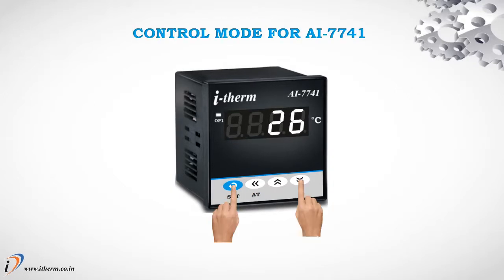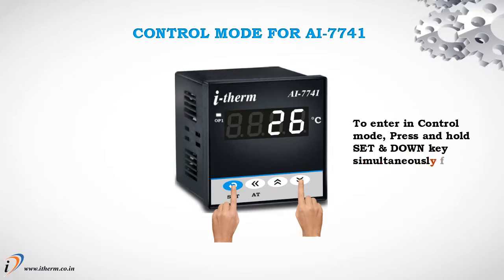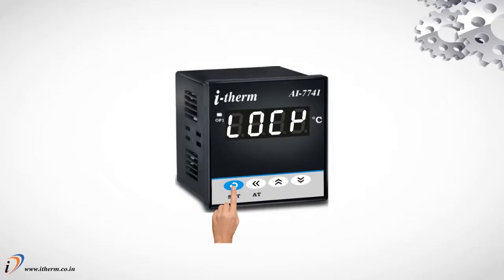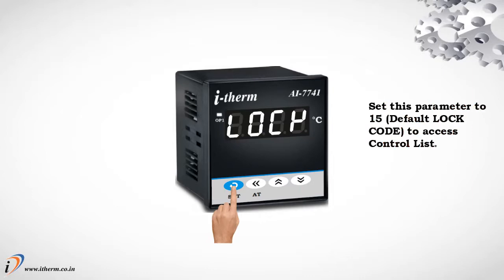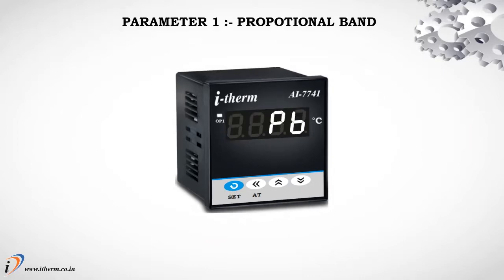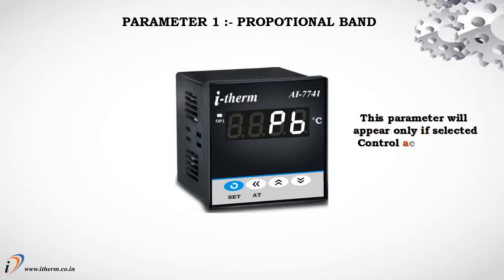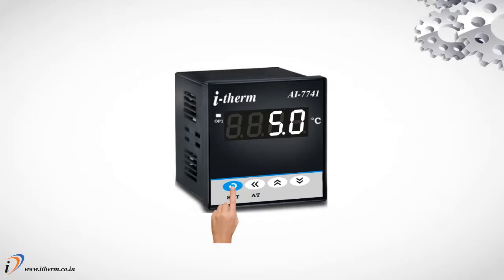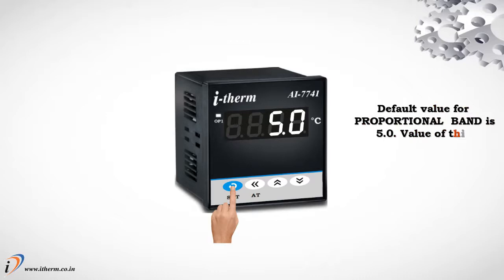Control mode for AI7741. To enter in control mode, press and hold Set and down key simultaneously for 3 seconds. Set this parameter to 15 to access control list. Parameter 1. Proportional band. This parameter will appear only if selected control action is PID. Default value for proportional band is 5.0. Value of this parameter is automatically set by auto-tune function.